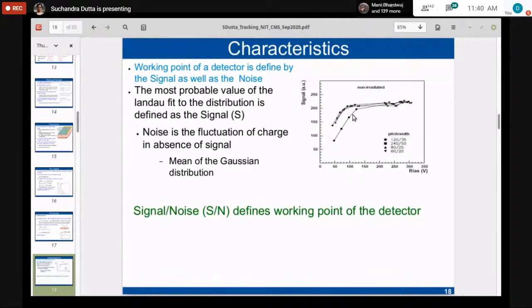And I showed before, there are different sources of noise, because when the detector is fully depleted and there is no external particle, in case of an ideal detector we should have noise 0, but that's not 0. So that is the way we measure it, as I mentioned. So signal over noise defines the working point of a solid state detector.